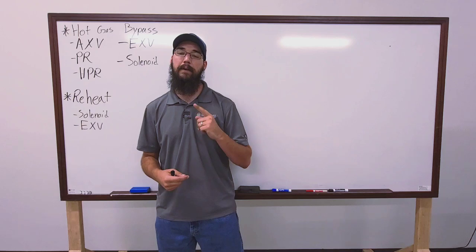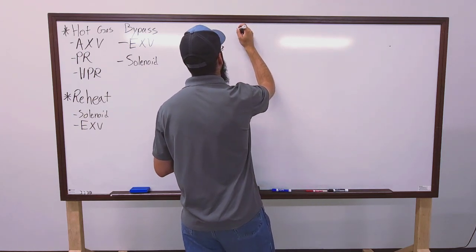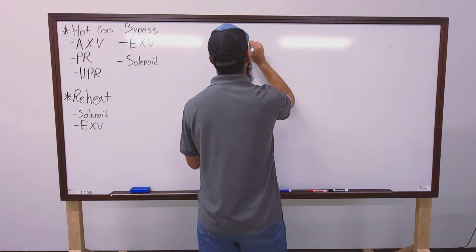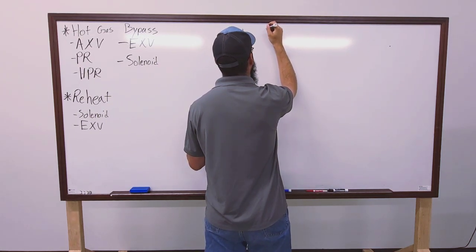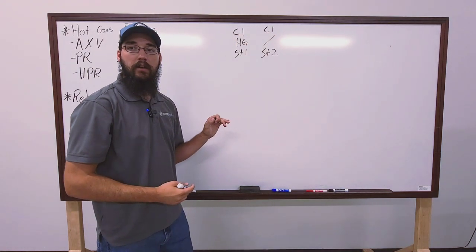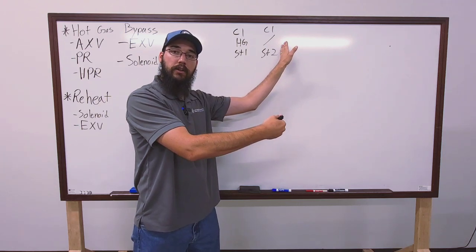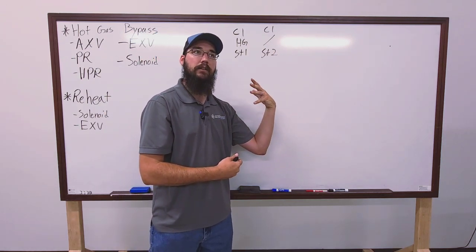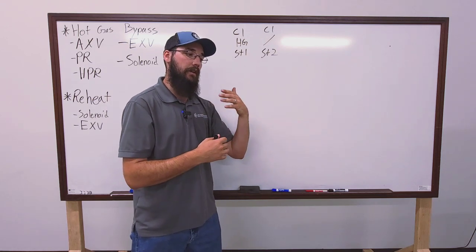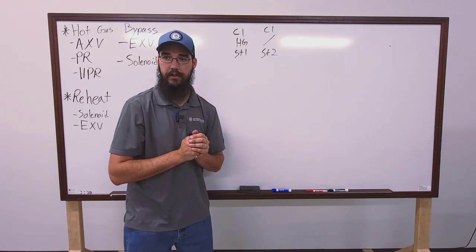As part of the staging on that system, circuit one has a hot gas bypass circuit and if you actually look at the staging in the book, it stages compressor one with hot gas, and that is stage one. And then stage two is just compressor one by itself, no hot gas. And the reason why they're doing that is this unit is controlling off of discharge air. So in RTUs, we'll take the same type of approach.